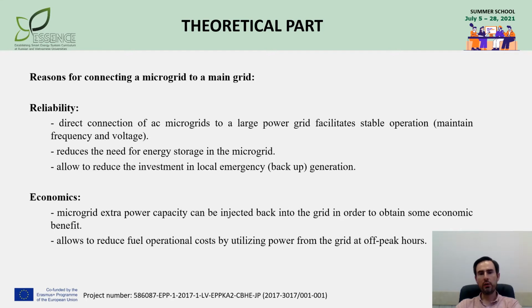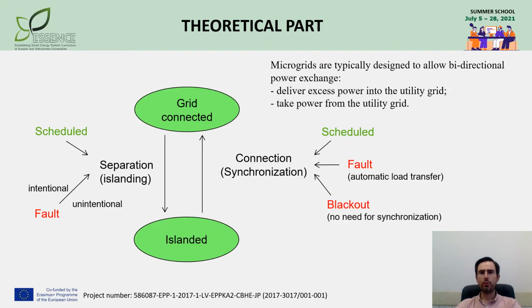Well, regarding the economics, the microgrids are typically planned with extra capacity with respect to the local load. This extra power capacity can be injected back into the grid in order to obtain some economic benefit. And also, the grid connection allows reducing fuel operation costs by utilizing power from the grid at night when electricity costs are low. There are two basic operating modes, grid-connected and islanded.